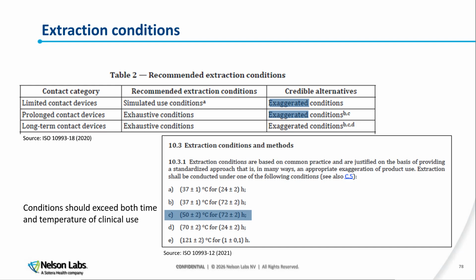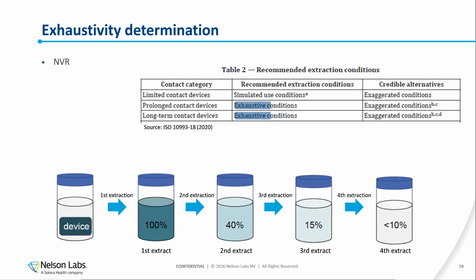In part 12, you see this excerpt below, it quickly shows what could be used as extraction conditions, but once again, part 12 is for biological tests, but we can use this, and in general we use this highlighted one, which is 50 degrees and 72 hours. Mainly the reason is that 37 degrees is also indicated as too low a temperature, and 70 degrees is quite a high temperature already, and is also a short duration, 24 hours. And then, yeah, if you go even further, 121 degrees, that's not good for many used materials. So 50 degrees, 72 hours.